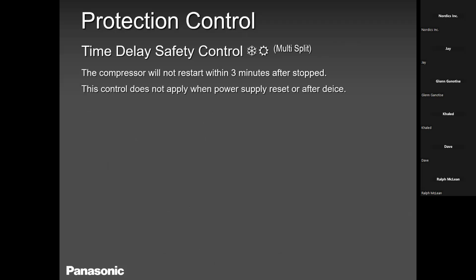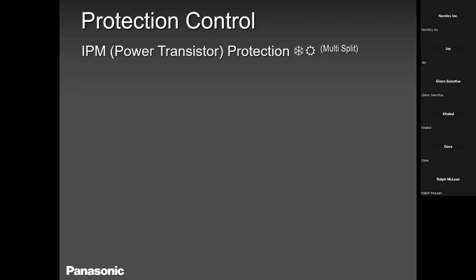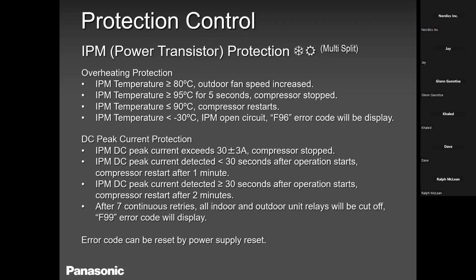Compressor always has a 3-minute delay. A 3-minute delay, and if you're waiting for those 3 minutes, it can be a little bit longer. But technically, if you switch off the unit and bring it back on, it's a 3-minute delay. IPM is the intelligent power module. It's built into the PCB, and basically it's pretty much driving the compressor. And if there's anything wrong with this board, you'll get an error of F90, F96, and those kind of things.